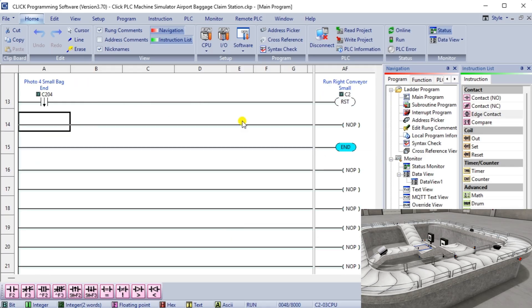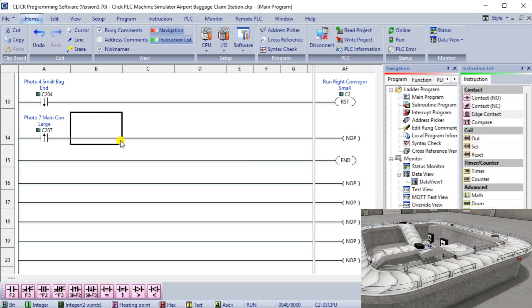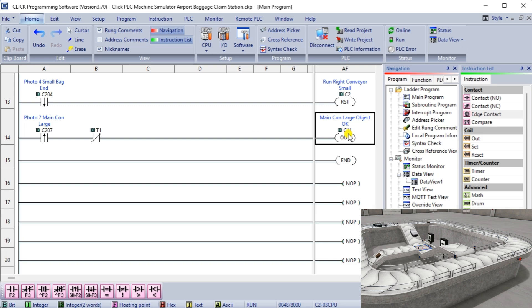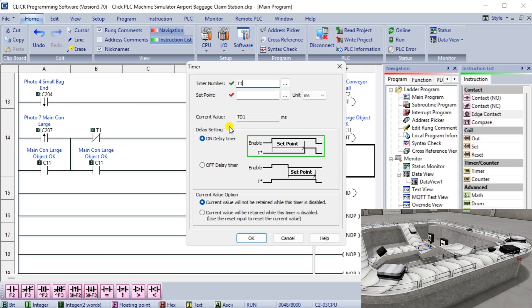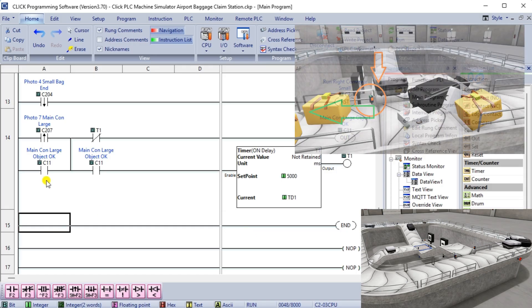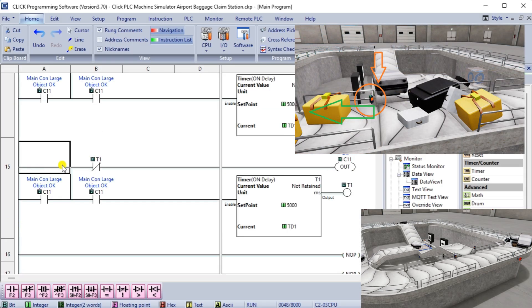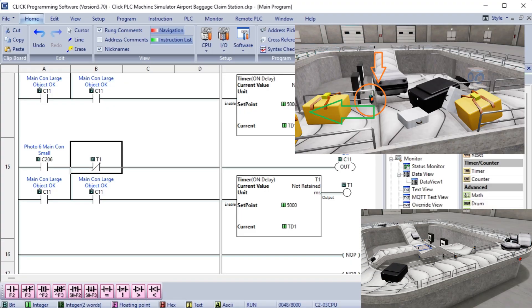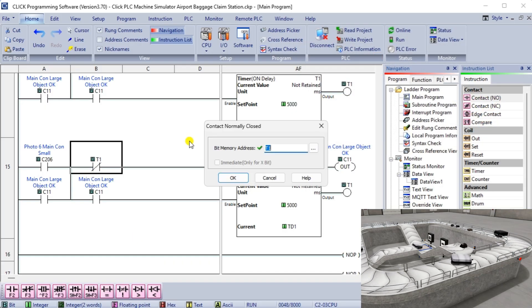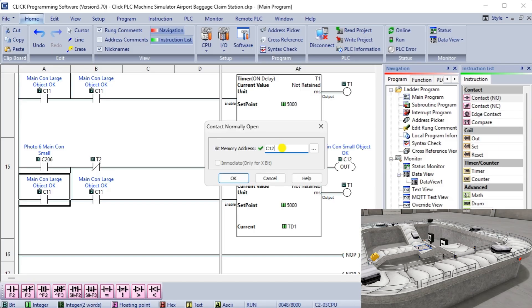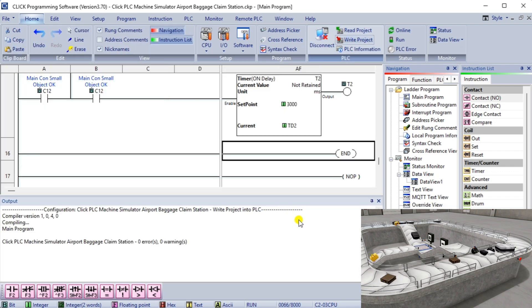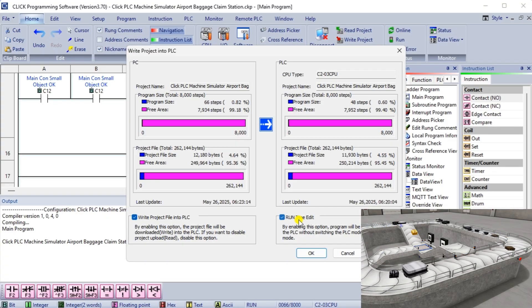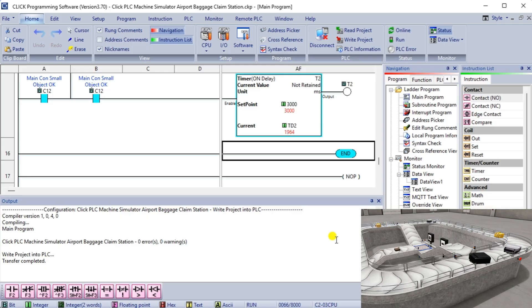The ladder logic rung program for the objects in the way on the main conveyor is similar. On the leading edge of photo 7 and not the time delay, we will set the internal bit C11 on to indicate objects are in the way, so no bags must be moved to the main conveyor. This is for large bags being moved to the main conveyor. The leading edge one shot is used because the photo 7 sensor must be moved to allow the program to work correctly. When photo 6 and not the time delay, we will set the internal bit C12 on to indicate objects are in the way for small bags being moved to the main conveyor. Save and download the PLC program. Our program is now complete. You can download this program below.